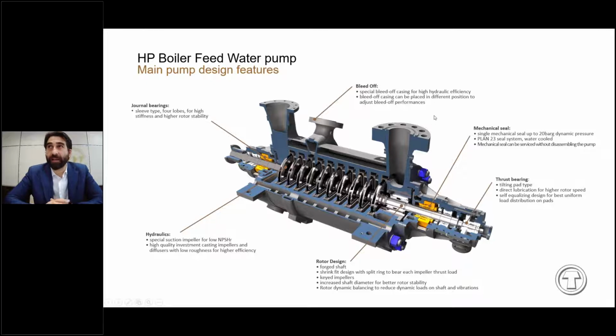The mechanical seal is a single mechanical seal, and it has been designed for up to 20 bar gauge of dynamic pressure, and it is flushed by a Plan 23 seal system, water cooled, and can be serviced without disassembling the pump, but only disassembling the bearing supports. Inside the bearing supports, we can find the thrust bearing, which is used to bear the residual axial thrust that is partially balanced by the balance drum installed on the rotor.